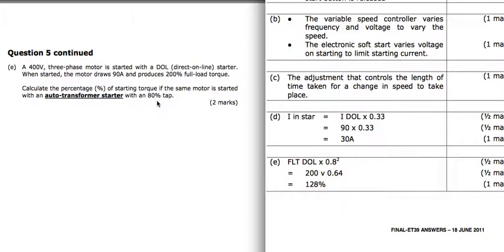It's that 80% squared times this 200. So it's the reduction in voltage squared, here we are at 0.8 as a decimal, so 80% is 0.8. 0.8 squared, which is 0.64, times the 200 gives us 128% full load torque.